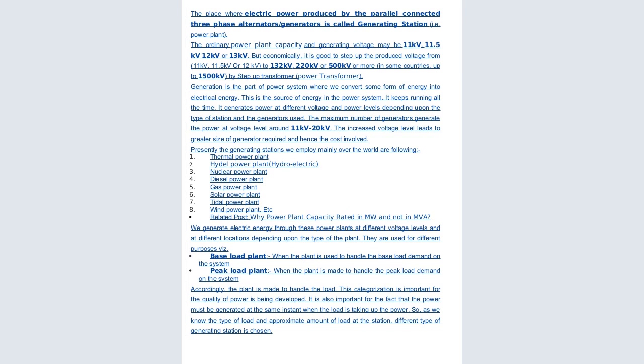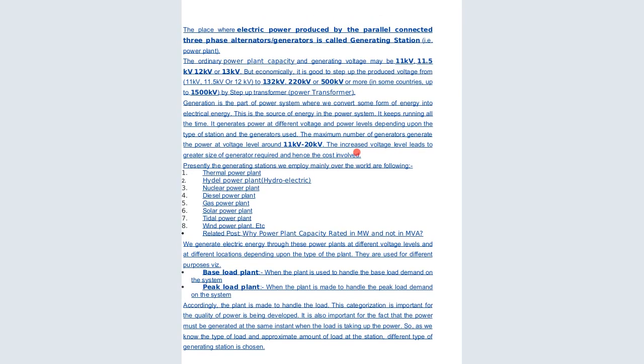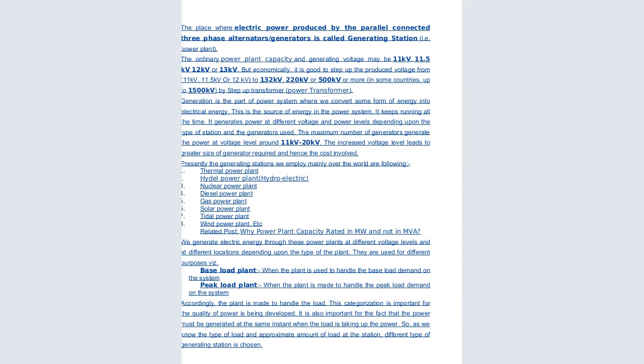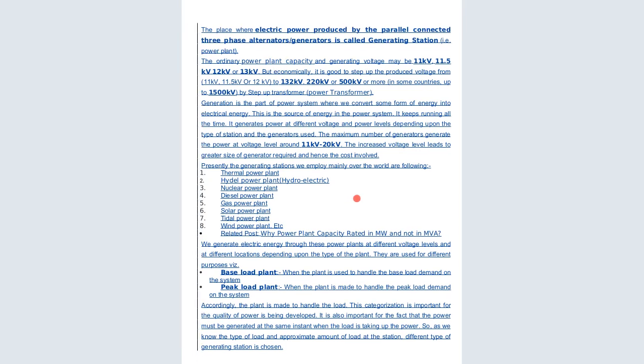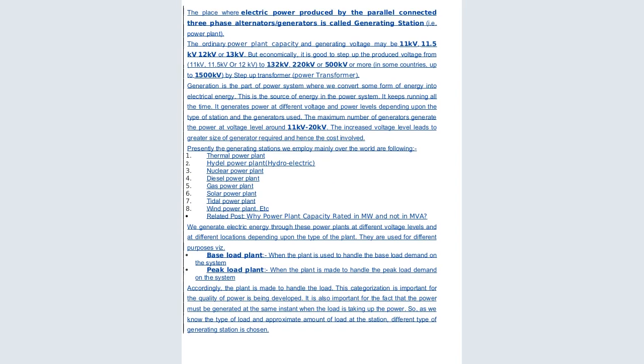So generation is the part of the power system where we convert some form of energy into electrical energy. This is the source of energy in the power system. It keeps running all the time. It generates power at different voltages and power levels depending upon the type of the station and the generators used. The maximum number of generators generate power at a voltage level around 11 kV. The increased voltage level leads to greater size. So presently, the generating stations employed mainly over the world are thermal plants.